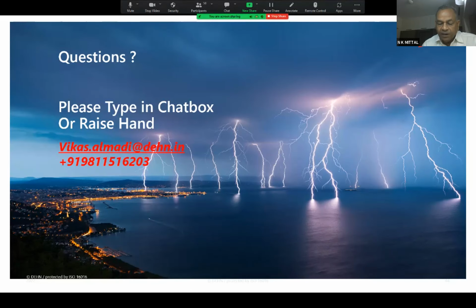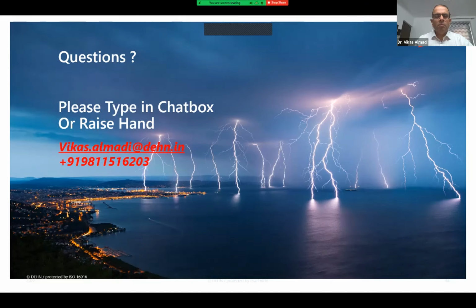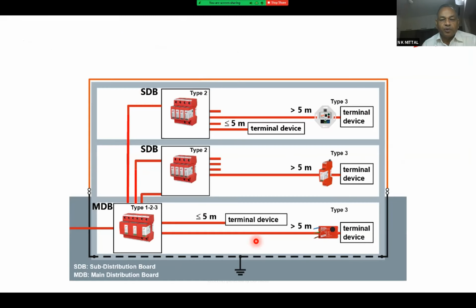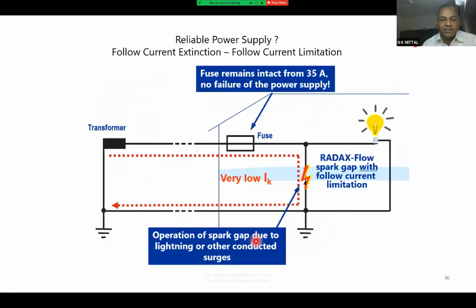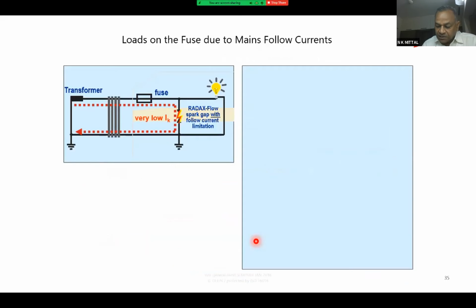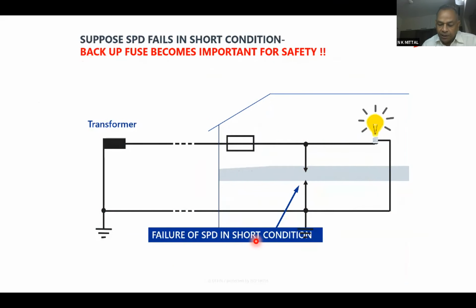That is point number 1. This I couldn't understand. Number 2, we have SPDs available, as you have rightly said, spark gap and MOV. MOV basically for the 8/20 microsecond curve, and the other one for the 10/350 microsecond curve. But we have SPDs available in the market many times. They call it 3+1 or 4+0. Many times we are using 4+0 also. So what is the basic difference between 4+0 and 3+1? What are the places where you suggest to use 3+1 or 4+0? Point number 2.